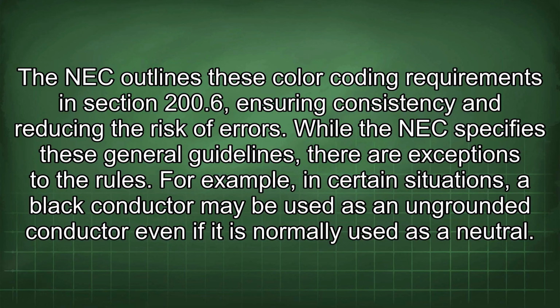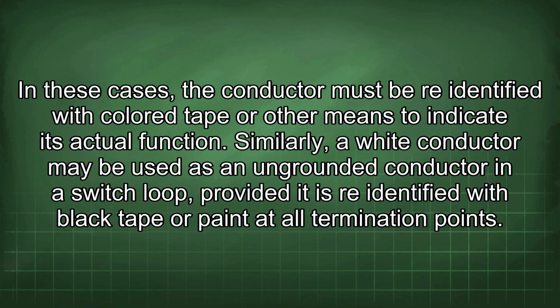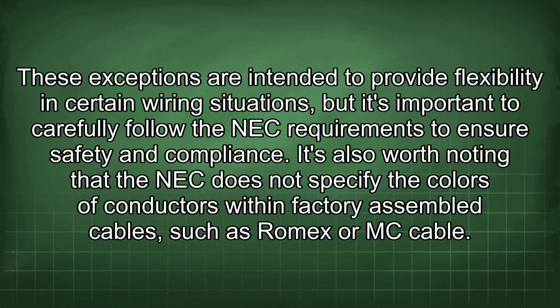For example, in certain situations, a black conductor may be used as an ungrounded conductor even if it is normally used as a neutral. In these cases, the conductor must be re-identified with color tape or other means to indicate its actual function. Similarly, a white conductor may be used as an ungrounded conductor in a switch loop, provided it is re-identified with black tape or paint at all termination points. These exceptions are intended to provide flexibility in certain wiring situations, but it's important to carefully follow the NEC requirements to ensure safety and compliance.